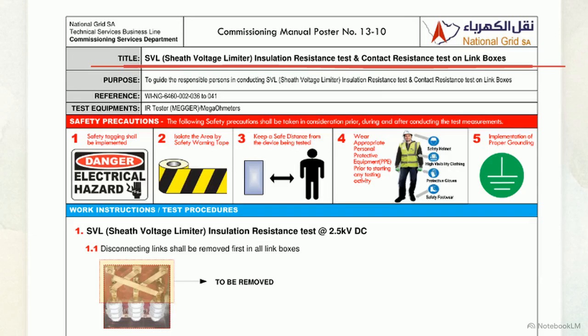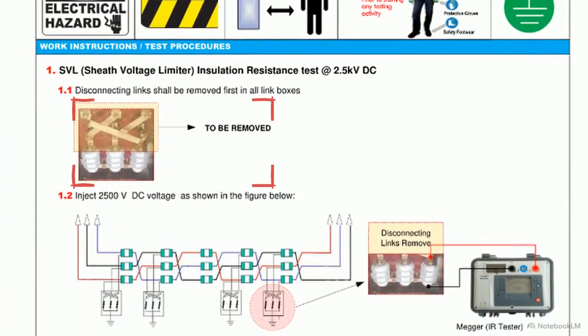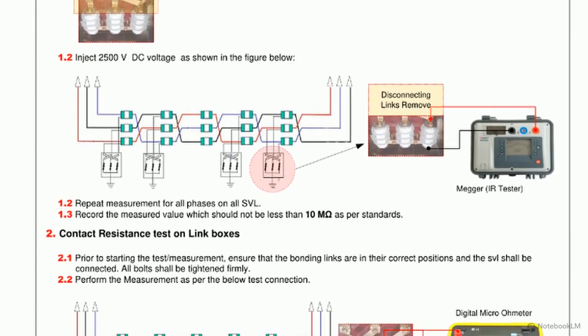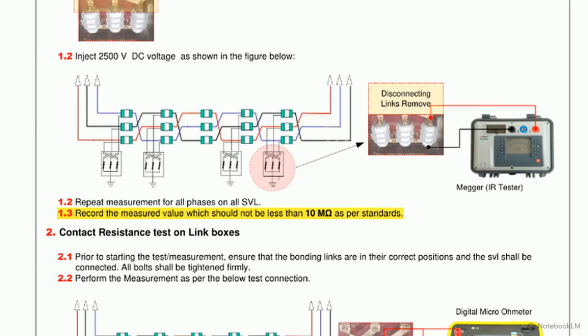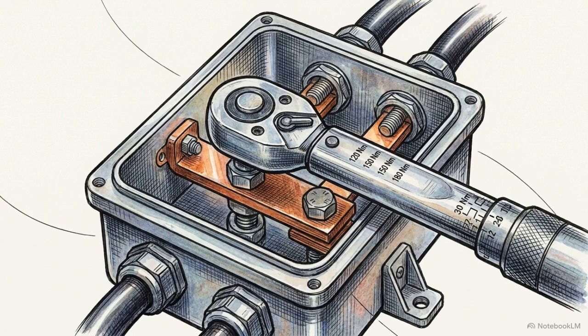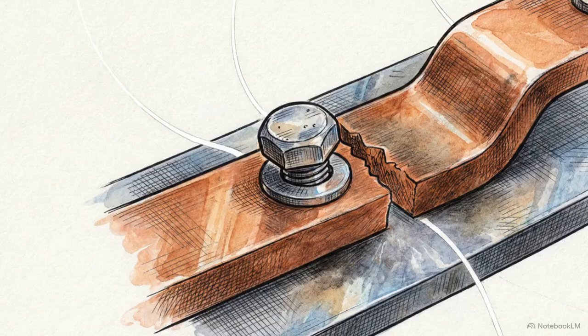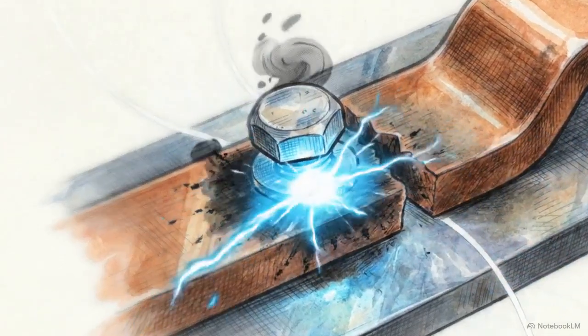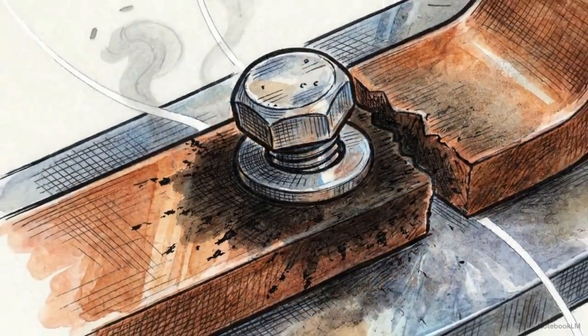This diagram demonstrates Test 13.10 for sheath voltage limiter insulation and link box contact resistance. To test SVL insulation, the disconnecting bonding links must be removed first. Technicians inject 2.5 kilovolts DC into each SVL point. The resulting insulation resistance must measure 10 megaohms or higher. Following the test, the bonding links are restored and tightened firmly to an approved torque. A micro-ohm meter then checks the connection points. Contact resistance must read near 0, strictly remaining at or below 20 microohms. A minor failure here can be catastrophic. Leaving a high-resistance contact or loose link compromises macro-level sheath protections, leading to severe sheath overvoltage risks when the grid is energized.